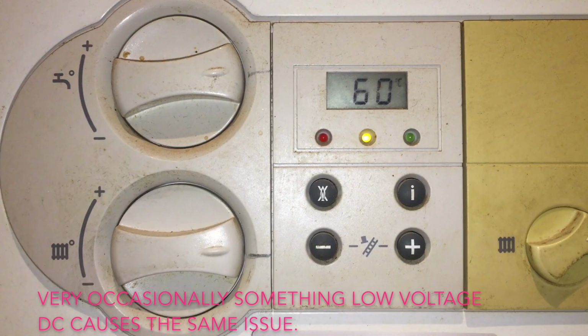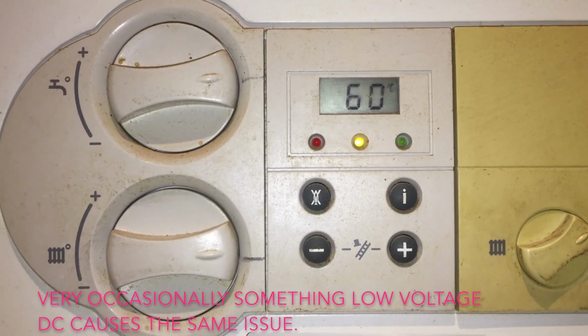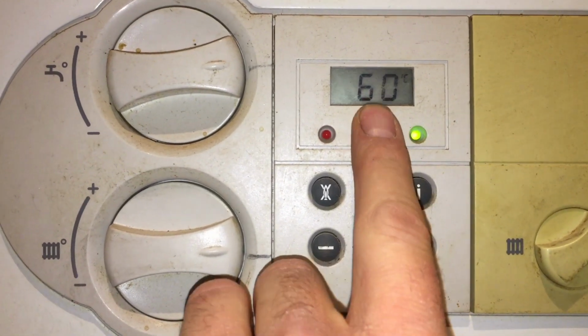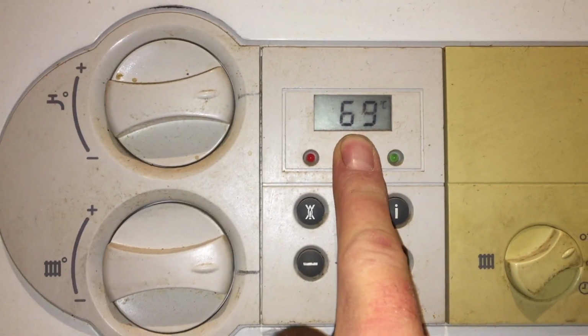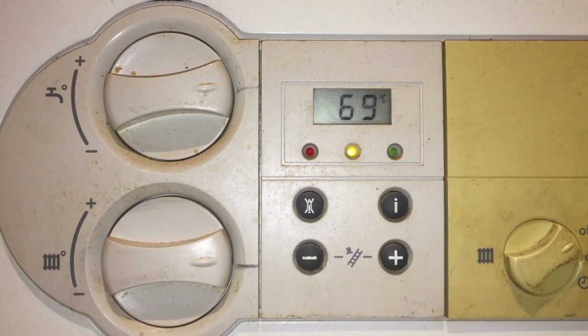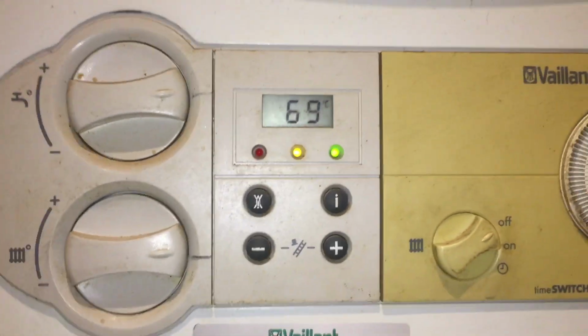And this is the telltale sign that you're correct, is when this temperature on the display is jumping around like this. Now, as you can see, it's jumping 10 degrees there. Now, this will eventually start doing some F70 fault codes as well.